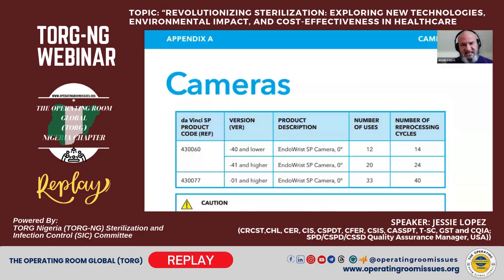Now, all of that to say that this device is being cleaned, is being utilized, is being inspected, it's going to be sterilized. But as you can see, this device also has a limitation of use. Depending on the version of the device, this device here in the United States costs 35,000 US dollars. And if you have the lowest available version, it can only be used 12 times or reprocessed 14 times. What does that reprocessing cycle mean?